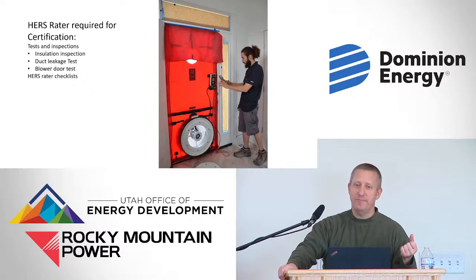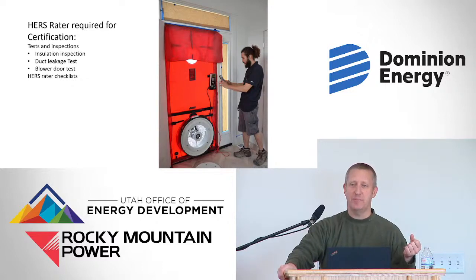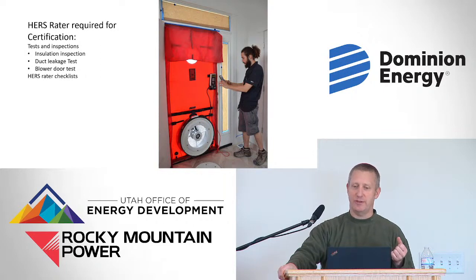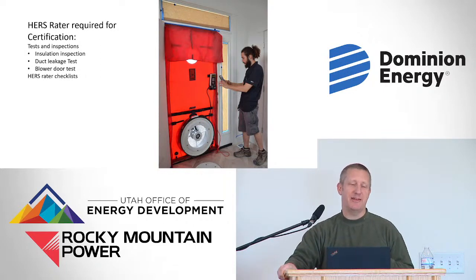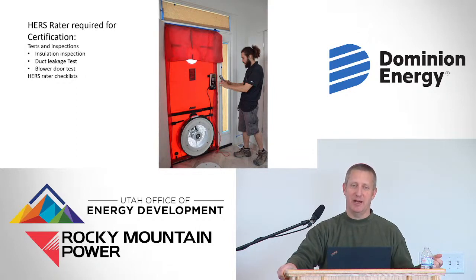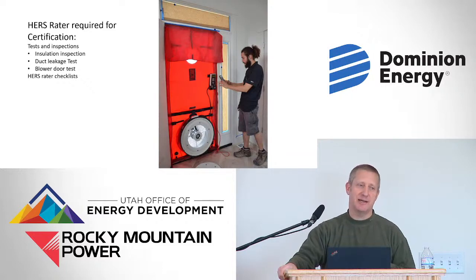Duct leakage test, and we like to do that typically at framing, because the system's far more accessible at that time. So if there are problems, it's a lot easier for us to see where they are, and a lot easier for those problems to be fixed. Once the system's buried in the house, you kind of have one option, and that's the Aeroseal.